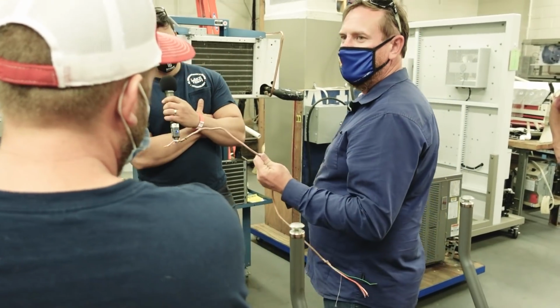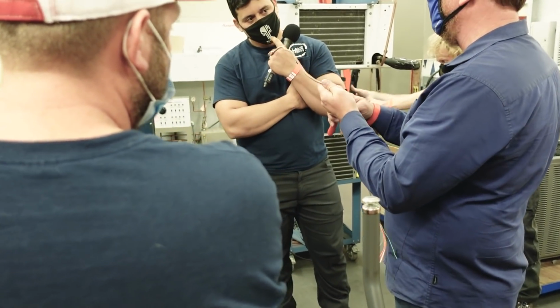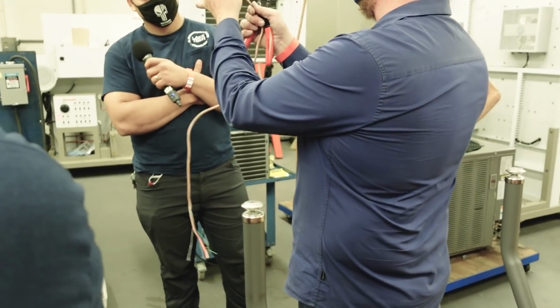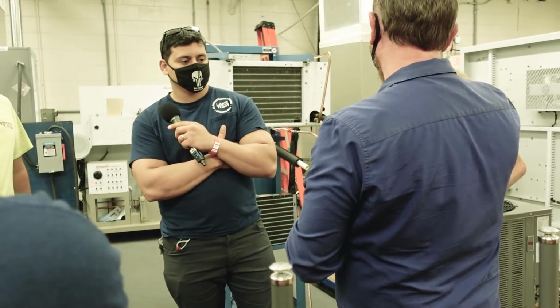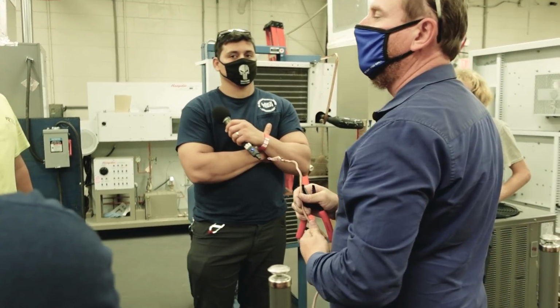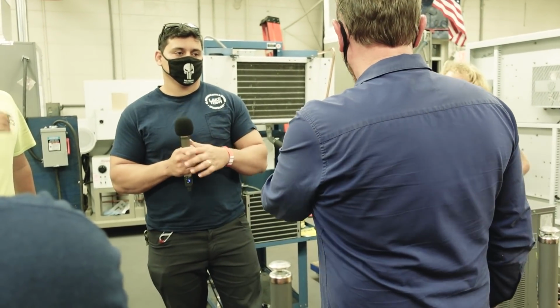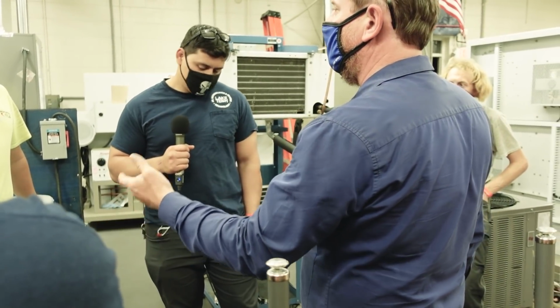So if you're having a short in a low voltage side, it blew a transformer, you're going to put a fuse, you're going to find it. You're going to inspect all of these little locations, all these spots, where it goes through metal. And then you can ohm out all your low voltage loads. You can ohm out the reversing valve. You can ohm out the contactor. You can ohm these out.